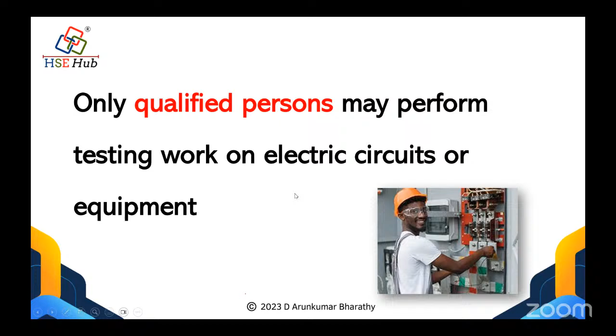Testing and measuring equipment has a lot of hidden hazards: electrocution, explosion, or flash. In fact, in industry, most arc flash incidents are not caused only by high voltage. I can say 50% are caused by the wrong measuring system and 50% maybe by poor equipment installation. So before sending a person for test and measuring, we have to educate the person, we have to train the person. Let's understand what traditional testing methods are available.